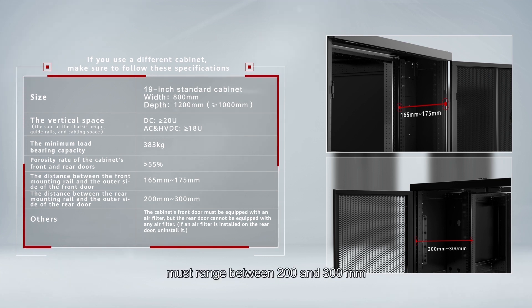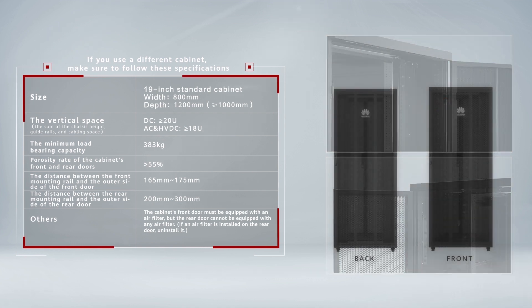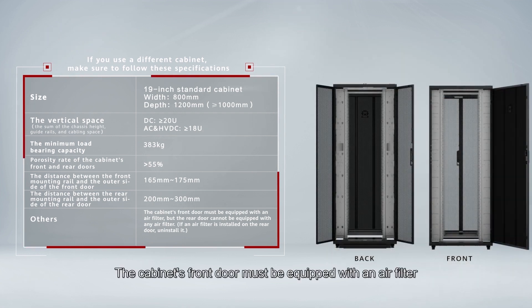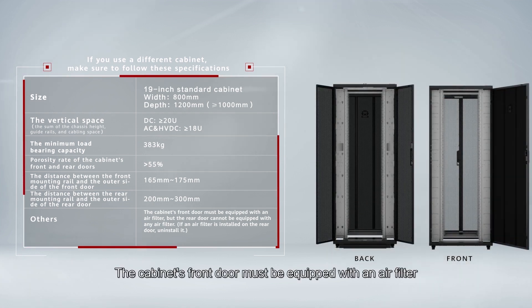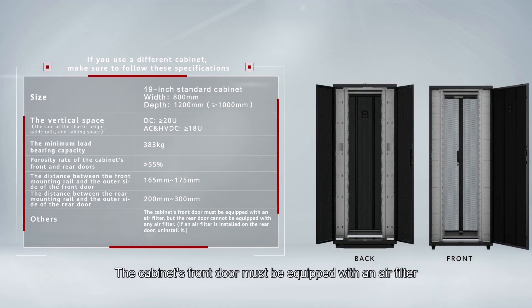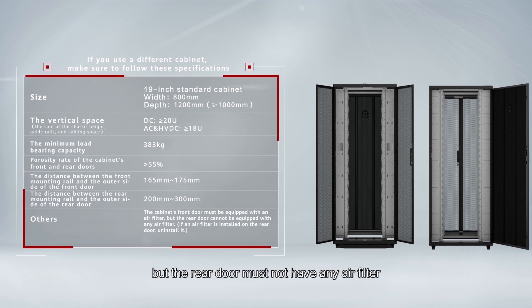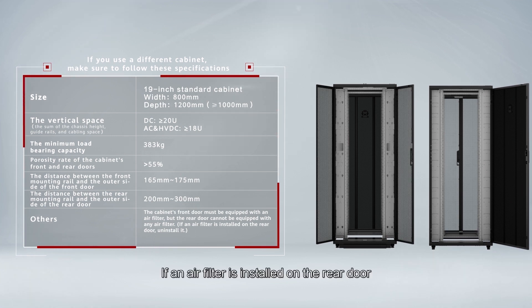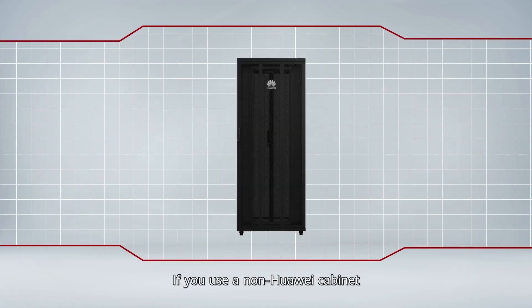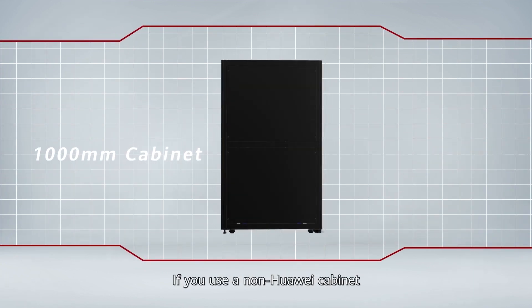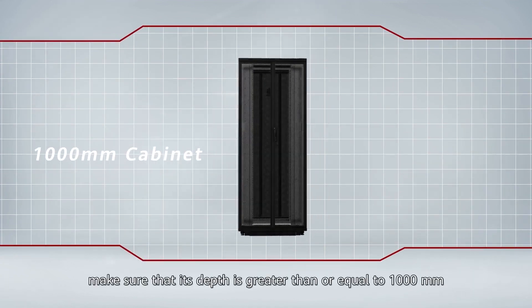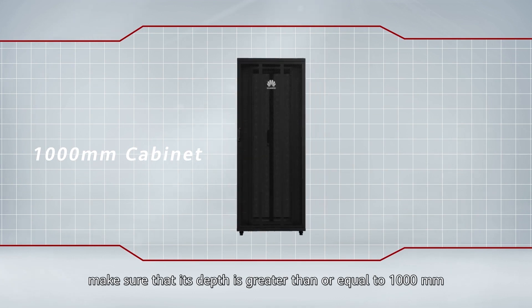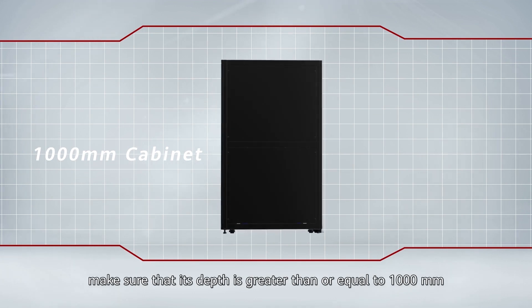The cabinet's front door must be equipped with an air filter, but the rear door cannot have any air filter. If an air filter is installed on the rear door, uninstall it. If you use a non-Huawei cabinet, make sure its depth is greater than or equal to 1000 millimeters.